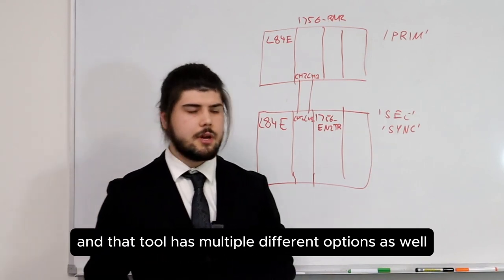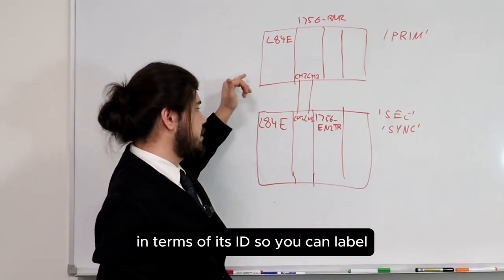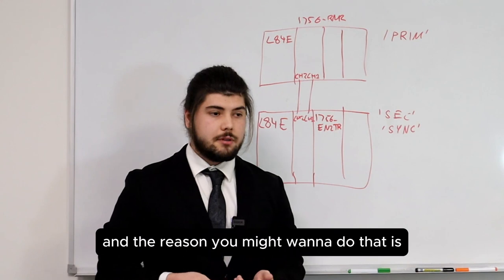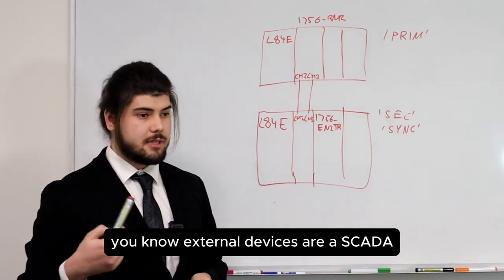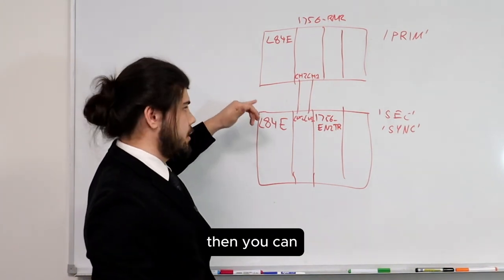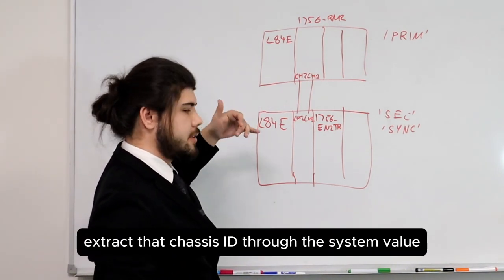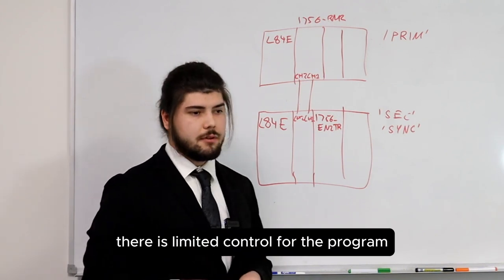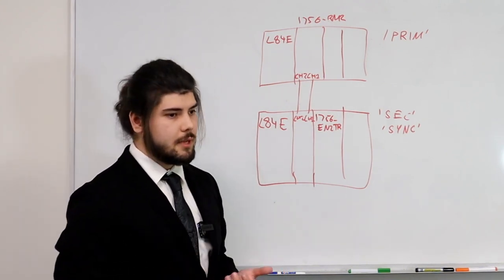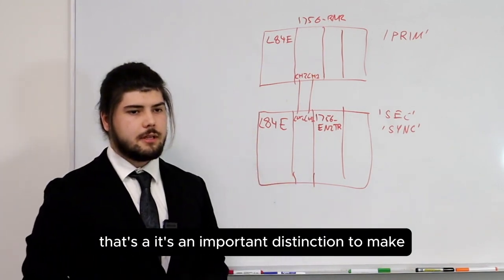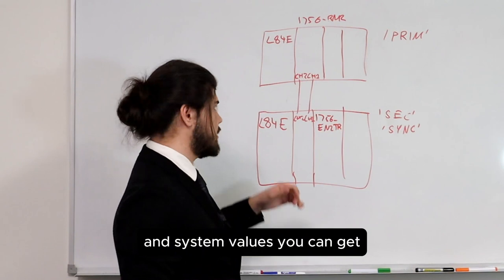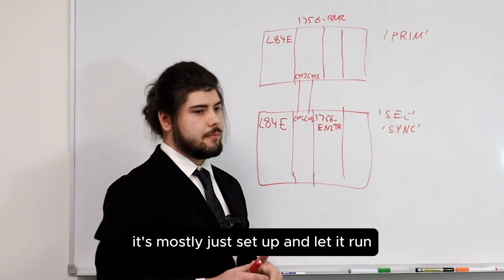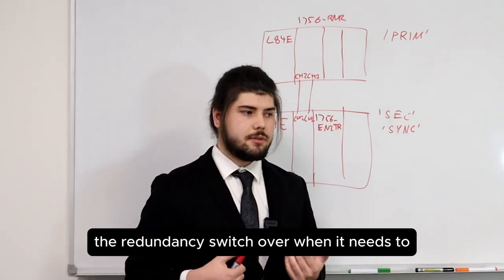In the RMCT tool there are multiple options. You can set a chassis ID description — labeling the primary as chassis A and the secondary as chassis B. If you're reporting to external devices or a SCADA to describe which chassis is in control, you can extract that chassis ID through the system value. You can also configure whether the program can actually control the PLCs. There is limited program control — mostly read values and system values — but through the program you can initiate a switchover. Mostly it's set up and let it run, and it will automatically handle the redundancy switchover when needed.